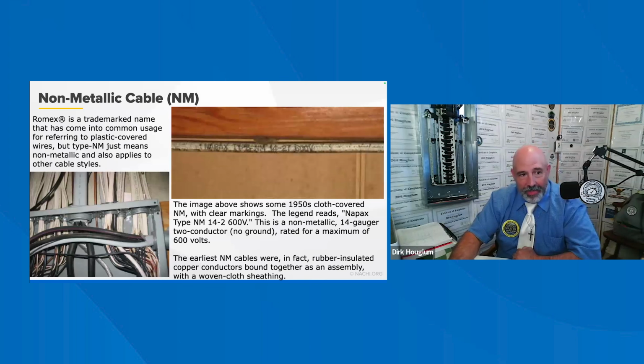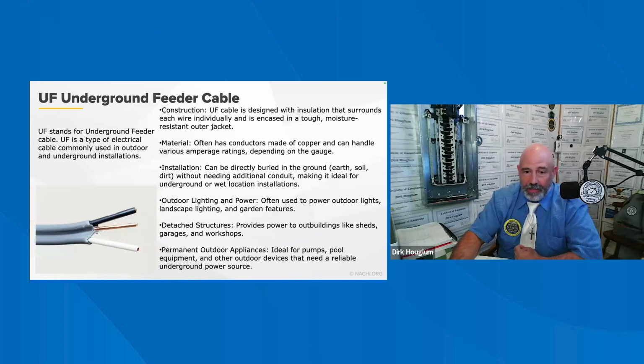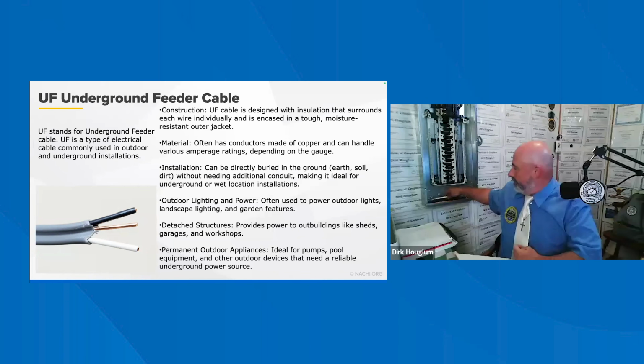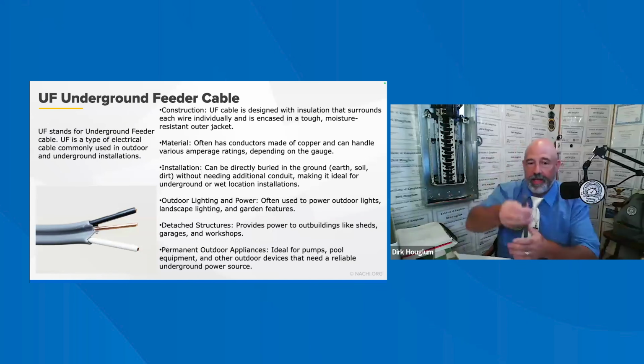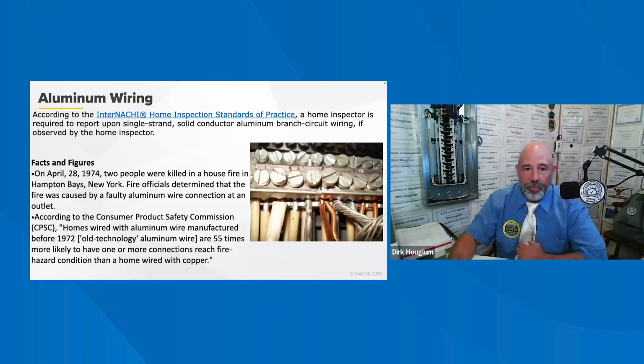Let's see here. The non-metallic cable, Romex was the trademark. We talked about this, 1950 cloth covered. NM was clearly marked. Make sure that you're checking all that stuff, and make sure that you do mention that this is older wiring, because that can cause some issues. The UF underground feeder cable, that is this stuff right here, looks just like that. Use that quite a bit.